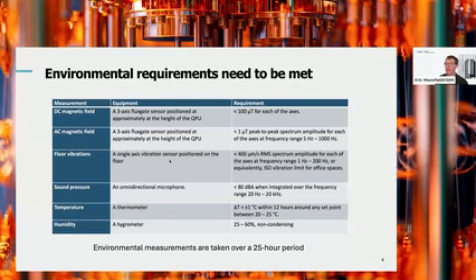We specify less than 80 dB, which is about as loud as a bar on a Friday night when everyone's having a good time. But some of our colleagues in Helsinki love Finnish death metal, and sometimes they blast it, and we can see noise in the signals when this happens. So we recommend wearing headphones while working with the system. Temperature-wise, we want to minimize temperature excursions in any 24-hour period, because many signal wires going in and out of the system are coated with Teflon, and if you remember the famous PTFE knee, temperature transients can cause subtle phase shifts in the extracted signals. Lastly, we want to avoid condensing humidity, both because it's bad for room-temperature electronics, and because we don't want to condense water on the cryostat when we open it while it's still cold.